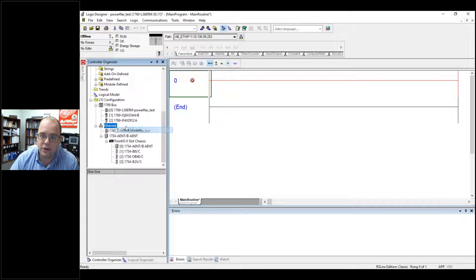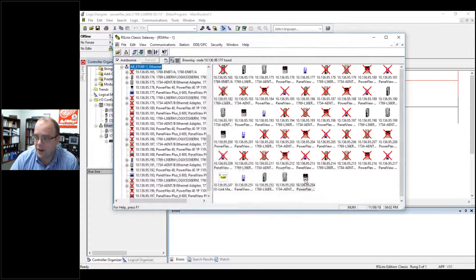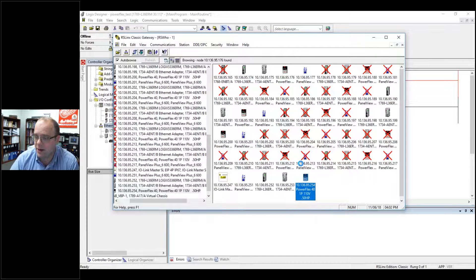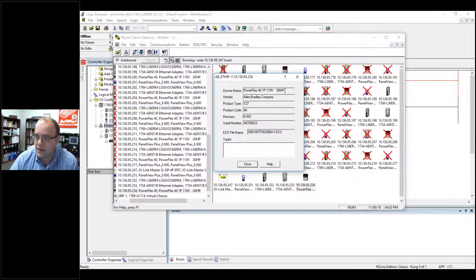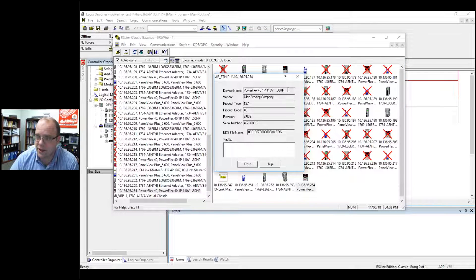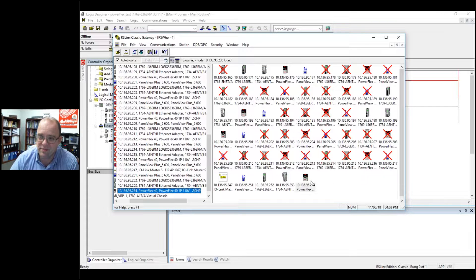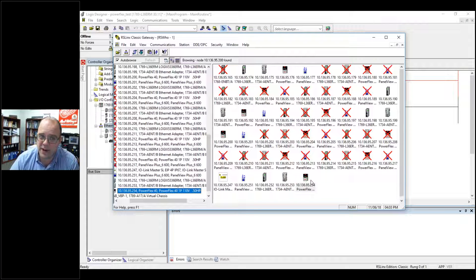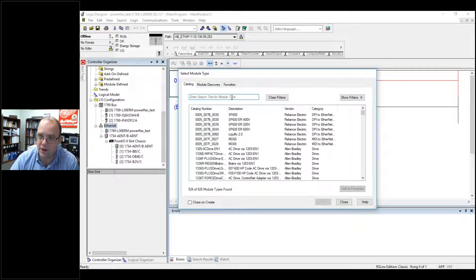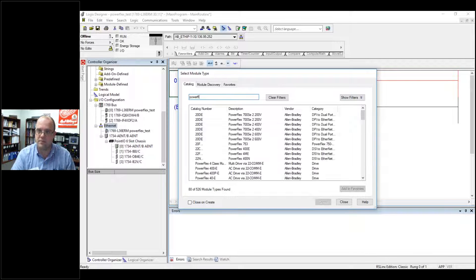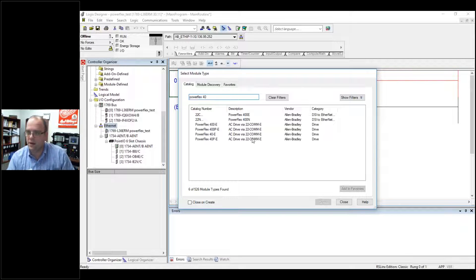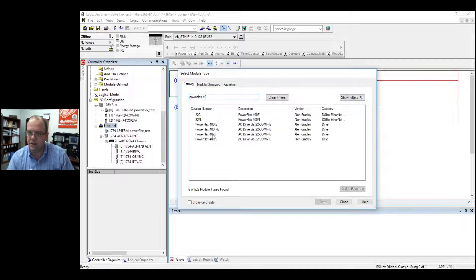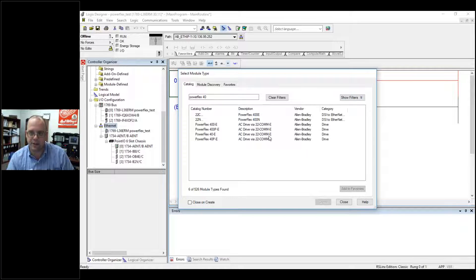If I right-click and add new module, it's important that if I go back to RSLinx and click on properties, it's going to tell you what type of revision and all that stuff. But this may not give you all the information. It's not telling you that it's communicating via 22-COMM-E Ethernet port. But if I type in PowerFlex 40, you'll see the 40PE. This is important. I have a 40, but notice that it's an AC drive by a 22-COMM-E port. Very important.